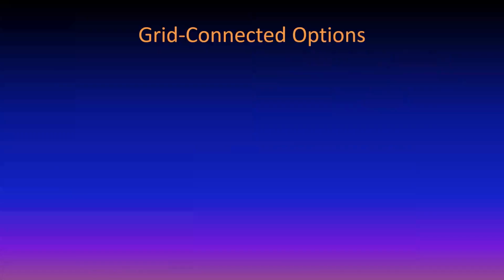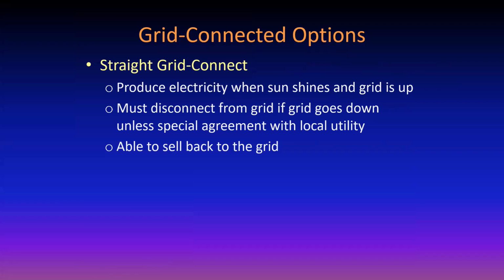So let's talk about some of the options for grid-connected systems. One of them is just straight grid connect. They make electricity when the sun shines and the grid is operating. If the grid goes down during the day when the sun is shining, the PV system has to go down as well, because otherwise, let's say the grid goes down because there's a wire broken or something like that, and they need to get a utility crew out there. A utility crew does not appreciate backfeed electricity from a photovoltaic system when they expect that line to be dead. So the inverters have to be sensitive to whether the grid is operational or not.